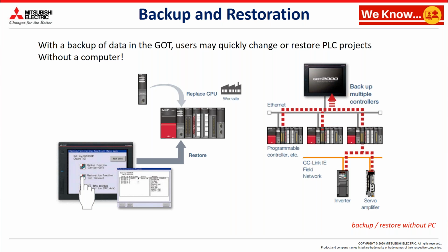With larger network configurations, devices like variable speed drives and servo amplifiers can also be backed up via the PLC. Besides making backups of multiple controllers connected on Ethernet, you can specify a trigger device, a day, a week, or time for automatic backup, reducing the time needed to back up each controller separately. This is a discipline we actively encourage customers to adopt, as without such backups, downtime in the event of errors is greatly impacted.